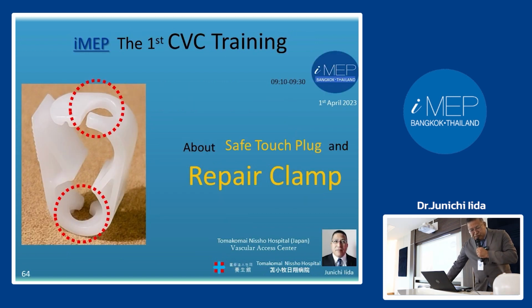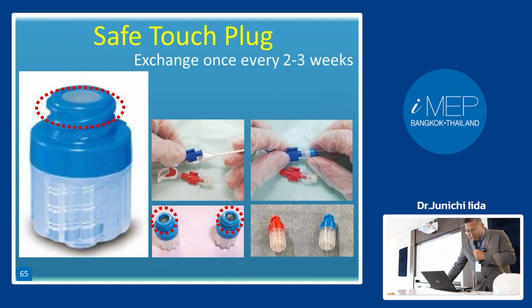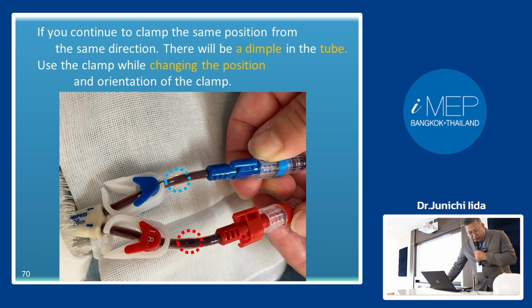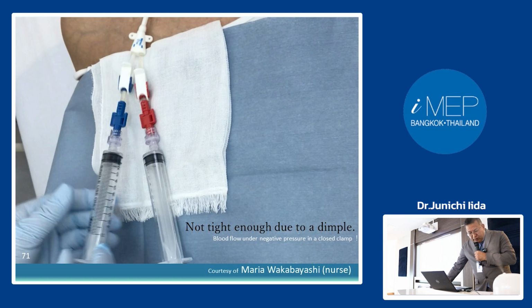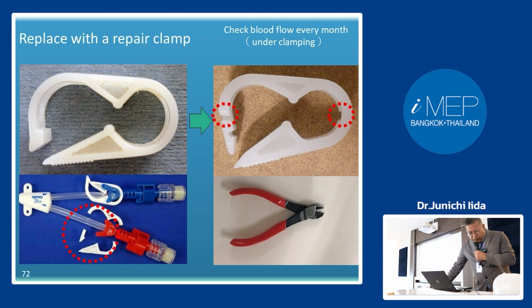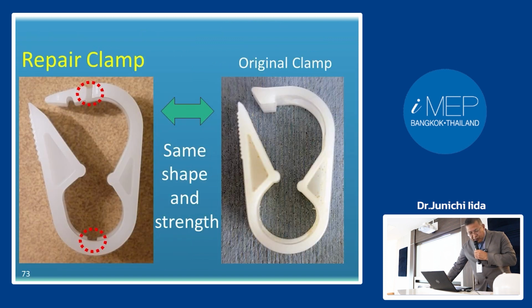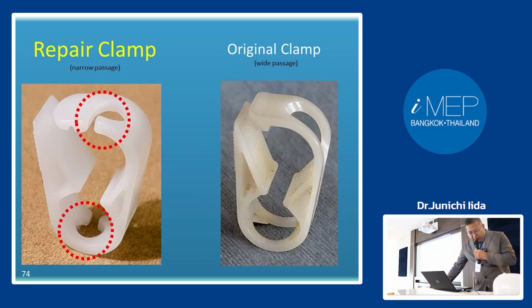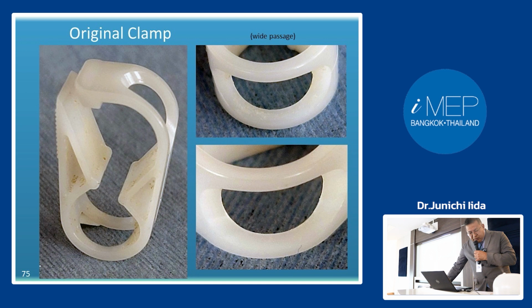Next, I'll explain the safe-touch plug and repair clamps. This is the safe-touch plug. If you continue to clamp the same part, there will be fixed dents in the tubes. In this case, while the clamps are still clamped, blood might leak. The clamps will deteriorate with frequent use. After catheter placement surgery, we use a syringe to occasionally check for defects in the original clamp. Original clamps and repair clamps have the same shape and strength. The repair clamp has two narrow catheter passages and slits, but the original clamp has a wide passage.